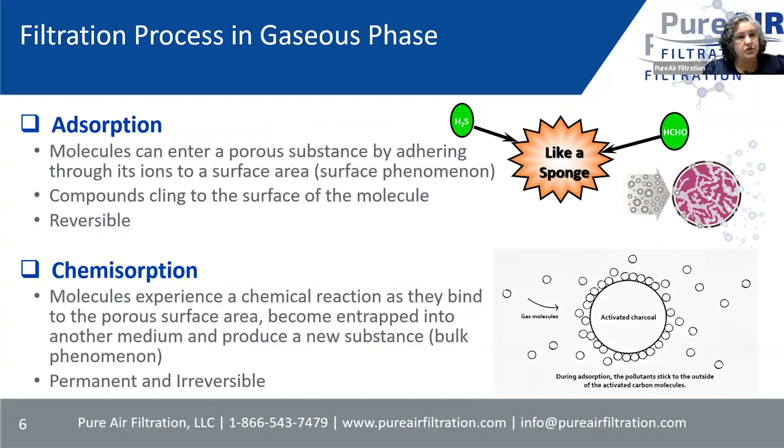Gas phase filtration — there are two types: adsorption and chemisorption. Absorption is more like a sponge: when the gas touches that media it will hold on to it, but it's not going to change the contaminant itself. If something changes in that area, like a lot more humidity coming through, it actually desorbs — so that's what happens with adsorption. It's mainly activated carbon or activated charcoal.